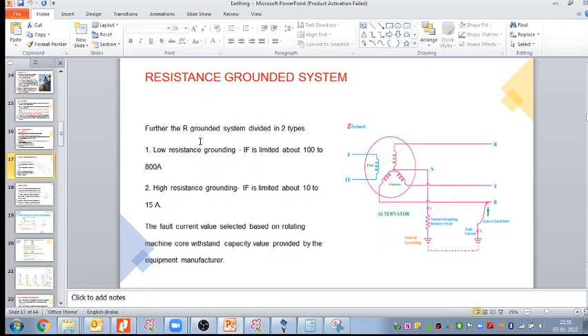For this, our grounding resistance grounding system is divided into two types: low resistance grounding and high resistance grounding. In low resistance grounding, we limit the current to about 100 to 800 ampere, and in high resistance grounding we limit it to 10 to 15 ampere. So we have to select how much current we want to limit based on the rotating machine's core resistant capacity. The fault current value is selected based on the rotating machine's core resistant capacity value provided by the equipment manufacturer.